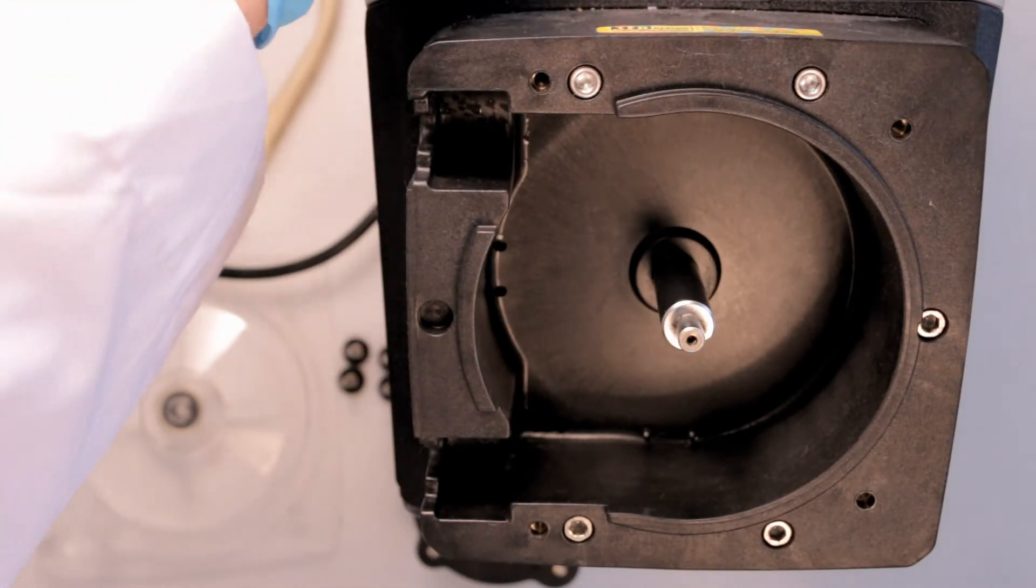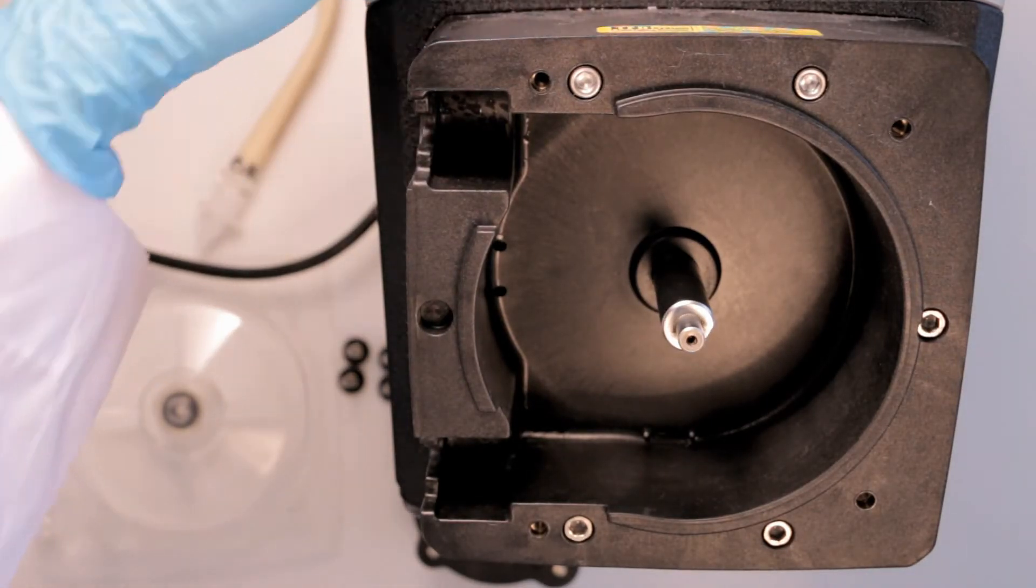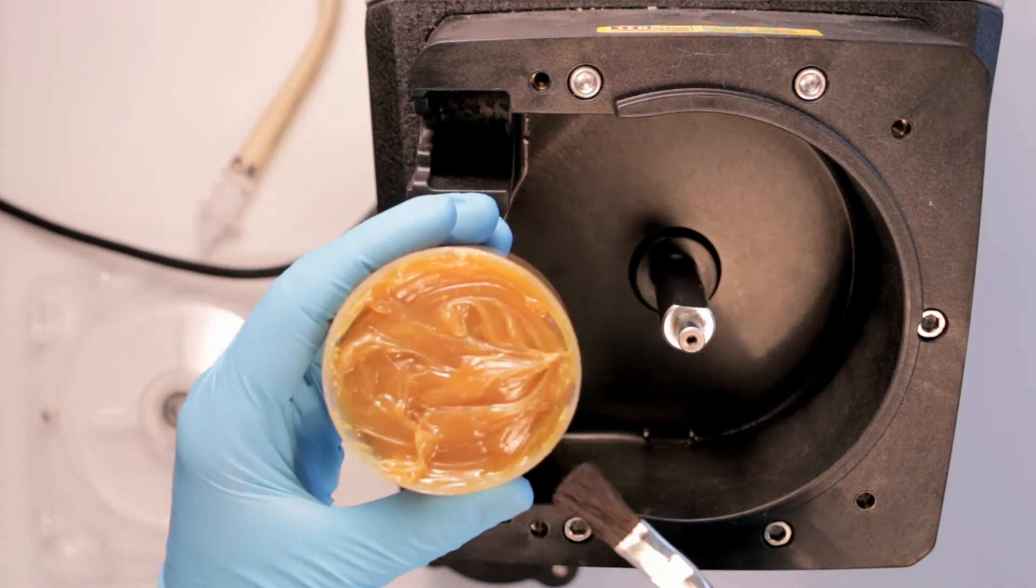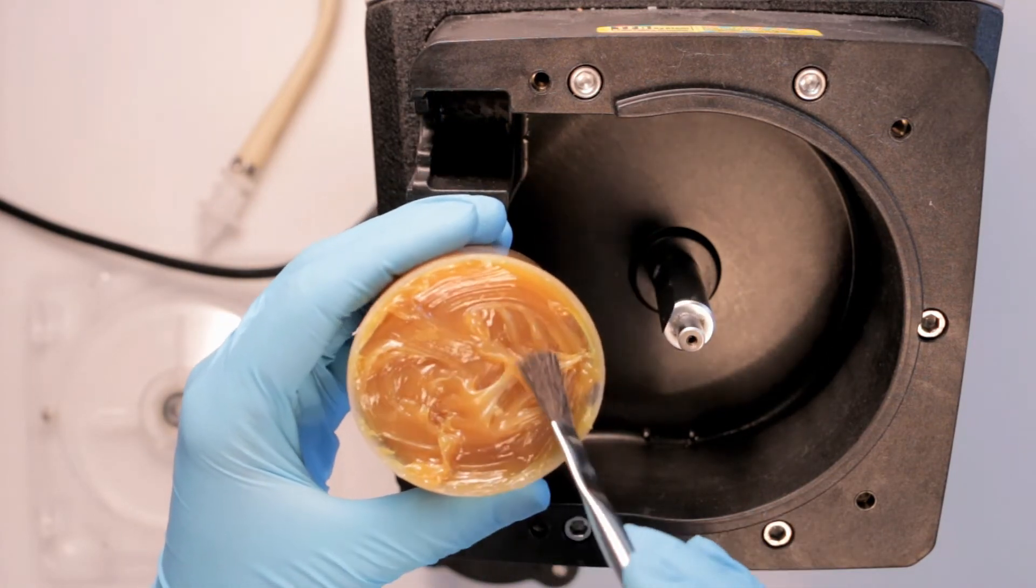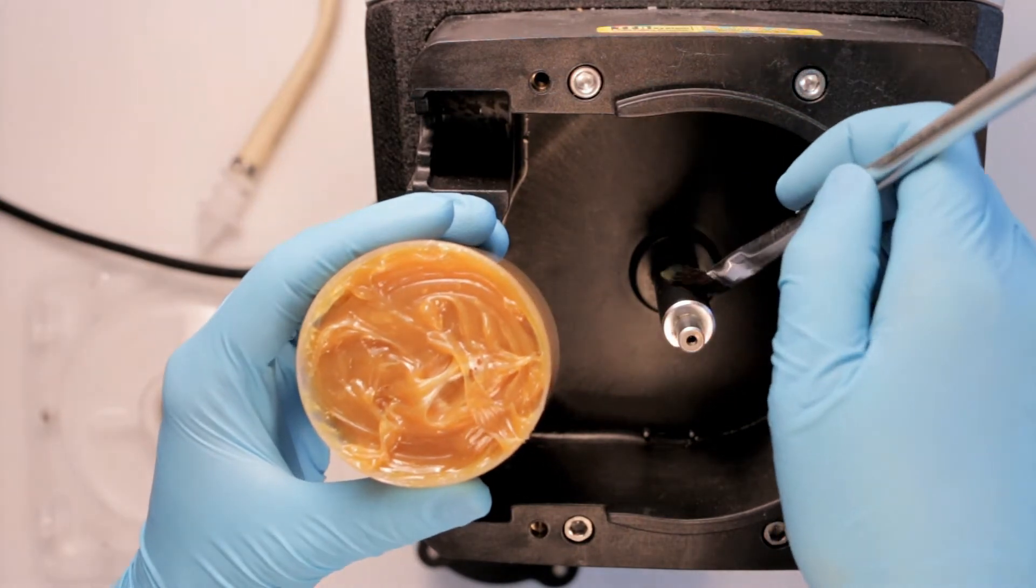In order to grease the motor shaft, press start to turn on the maintenance mode. This gets the shaft spinning at a low RPM. Take your high temp grease and paint it onto the motor shaft.